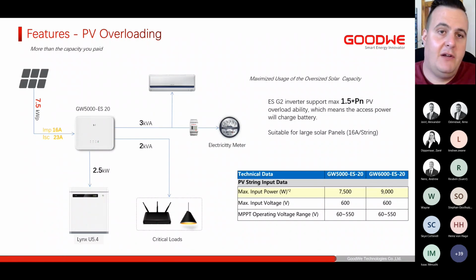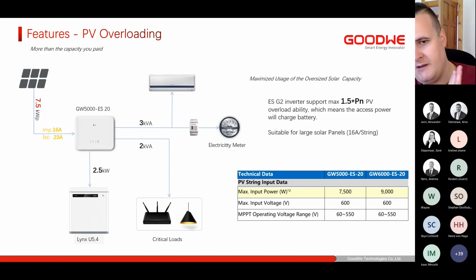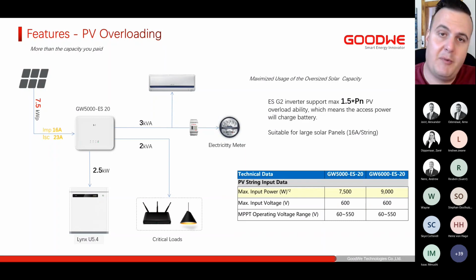So let's look at our PV overloading. The PV overloading on our inverters, we say 1.5 times the part number. In this example, we've got the 5 kilowatt ES. That can take 7.5 kilowatts of DC, and that is not just for oversizing, for bad weather or anything like that. That's actual usable DC. So I always like to explain it: it's a 5 kilowatt inverter and it has a 7.5 kilowatt MPPT. Well, 2 MPPTs divided gives you 7.5 kilowatts. So that's actual usable energy. In the day it can give you that 5 kilowatt AC as well as charge at 2.5 kilowatts.